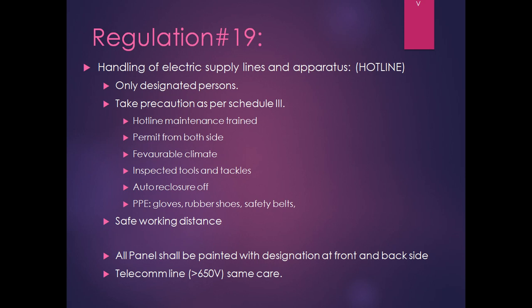Then if you again open the left hand side panel, that is basically you are opening the wrong panel. You should open the right hand side panel. So there is a chance of confusion. To avoid this, nowadays it is a standard practice to provide nomenclature at the front side as well as the back side. This regulation is saying that thing. Also, these precautions shall be taken while working on a telecommunication line whose nominal voltage is more than 650 volt.